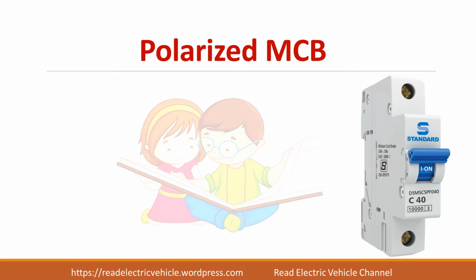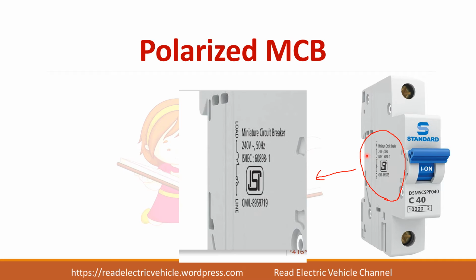Next we will see another MCB. You see in this side, so this is the front view, and you see in this side they have mentioned what is load and what is line here. It means that at the bottom you have to connect the line and at the top you have to give the load connection. So in this type of MCBs you cannot reverse the connection. So always line should be connected at the bottom and load at the top.